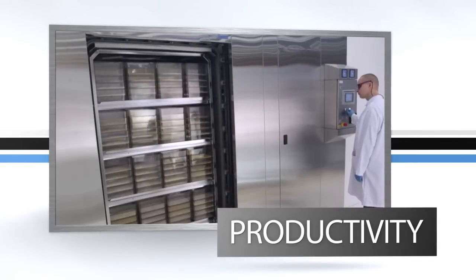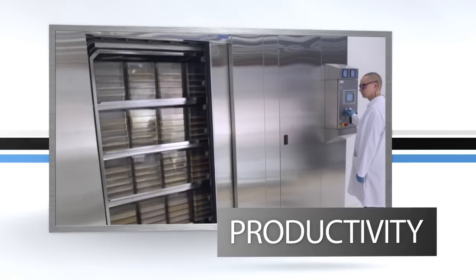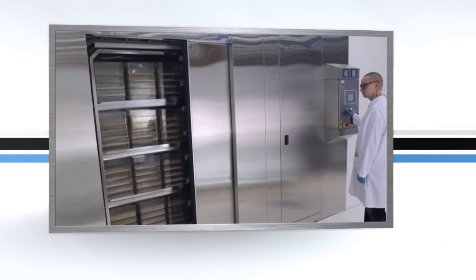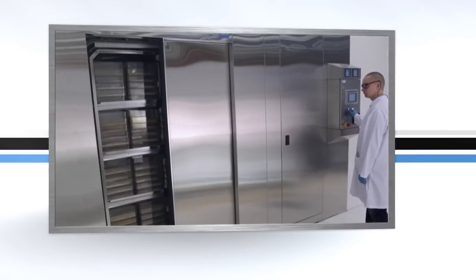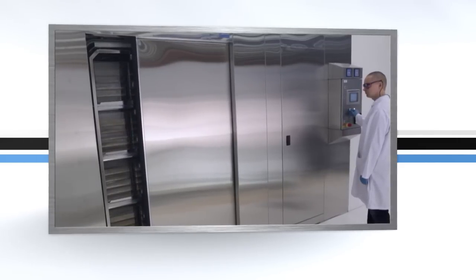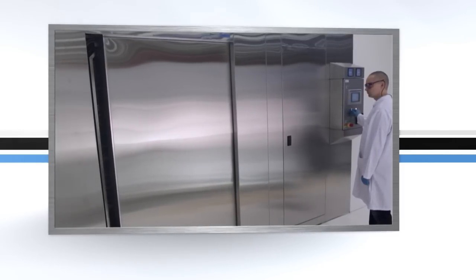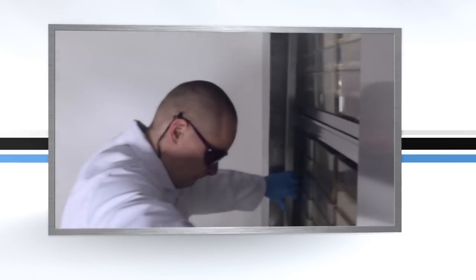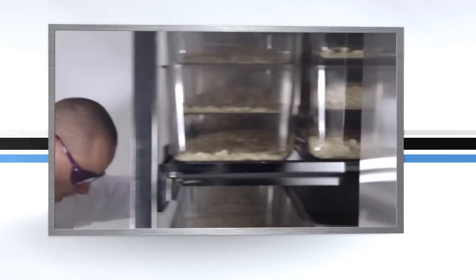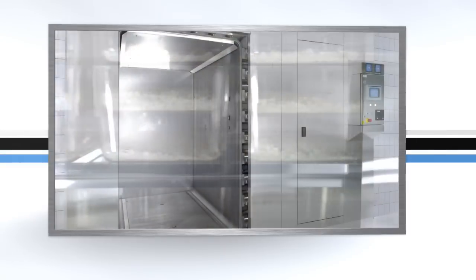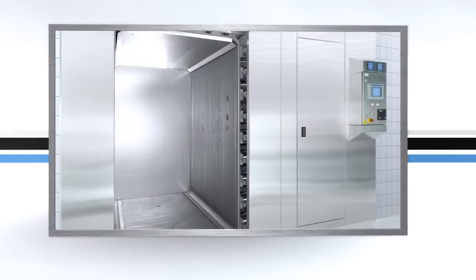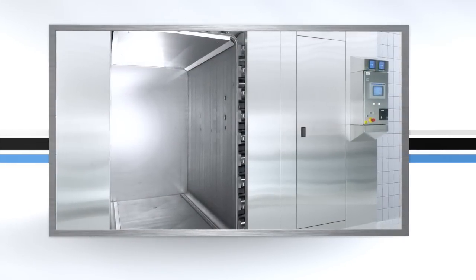Processing large quantities of cages, bottles, or other goods requires the ability to process large volumes at one time. The LSS series was designed with this level of productivity in mind. To meet the various load requirements required by different labs, the chamber can be manufactured in sizes ranging from 3.2 cubic meters to 8.5 cubic meters.